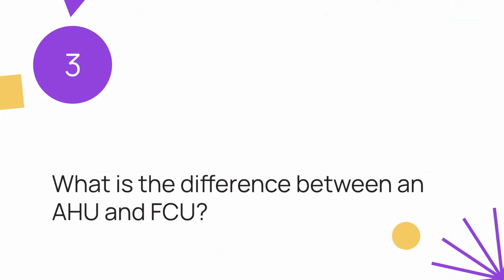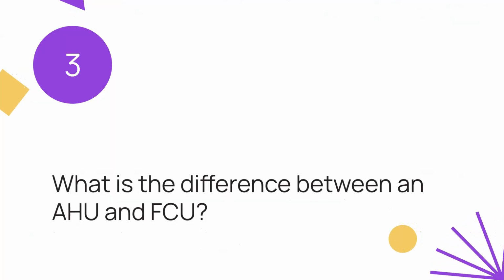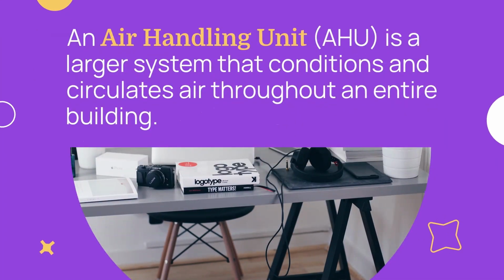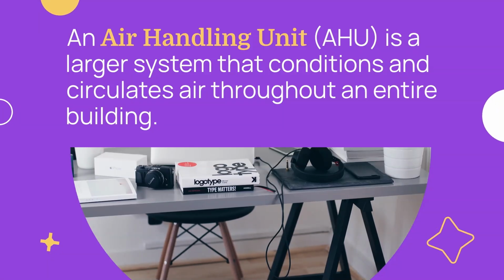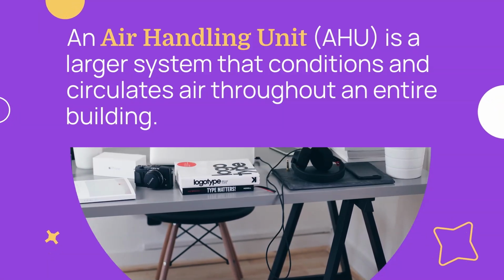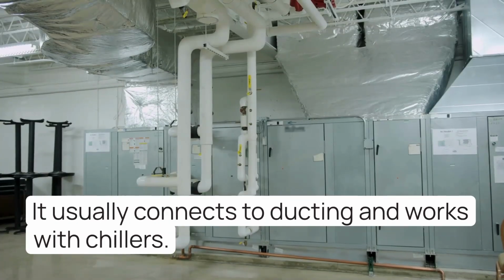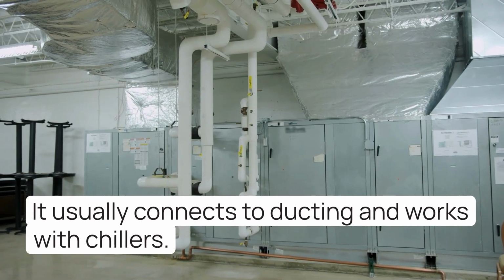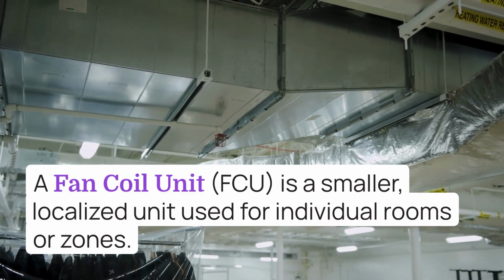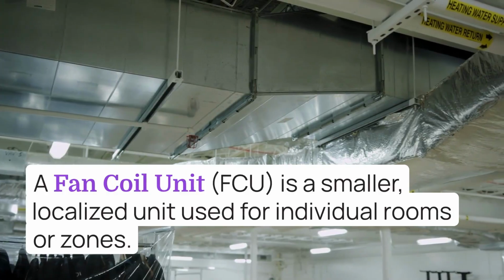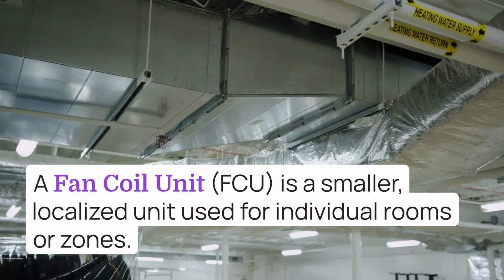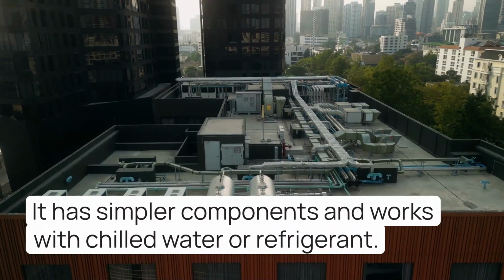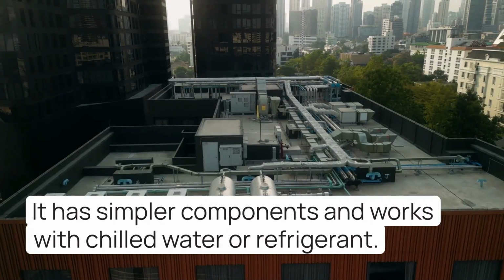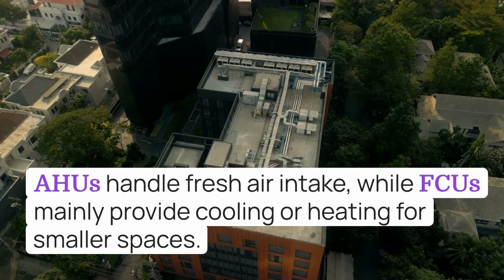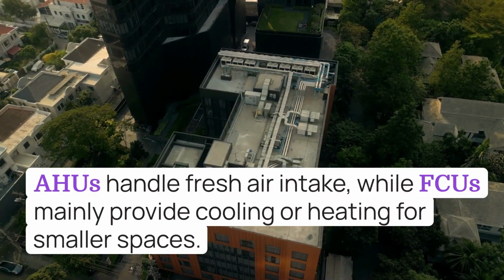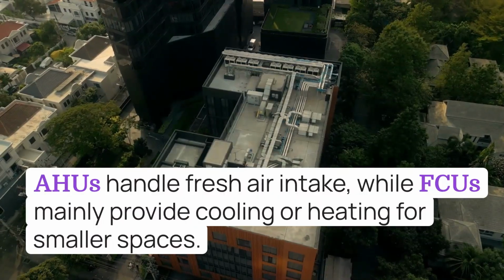3. What is the difference between an AHU and FCU? An air handling unit, AHU, is a larger system that conditions and circulates air throughout an entire building. It usually connects to ducting and works with chillers. A fan coil unit, FCU, is a smaller, localized unit used for individual rooms or zones. It has simpler components and works with chilled water or refrigerant. AHUs handle fresh air intake, while FCUs mainly provide cooling or heating for smaller spaces.